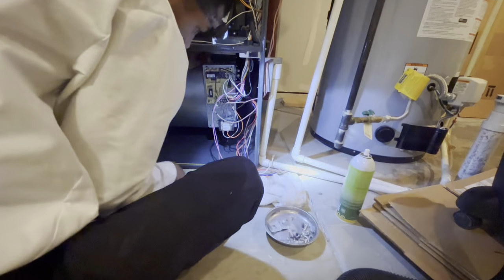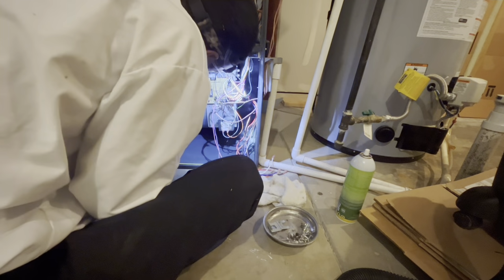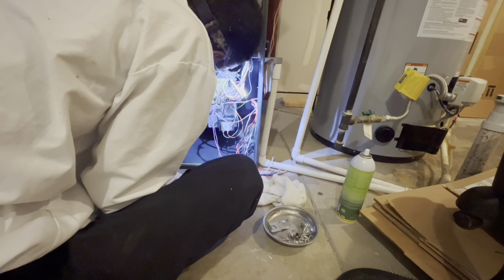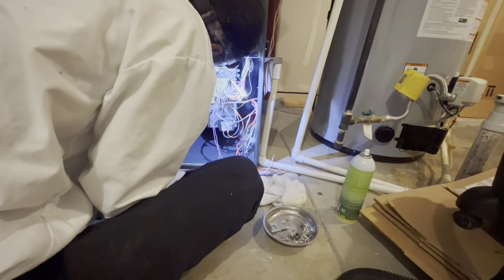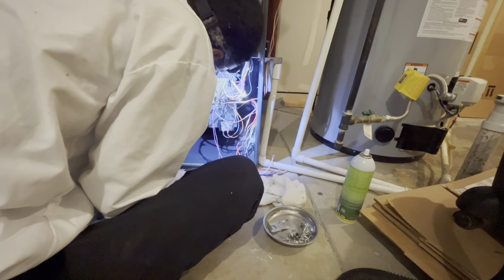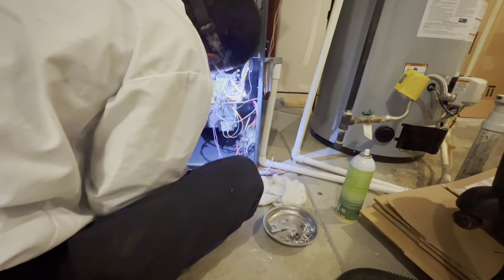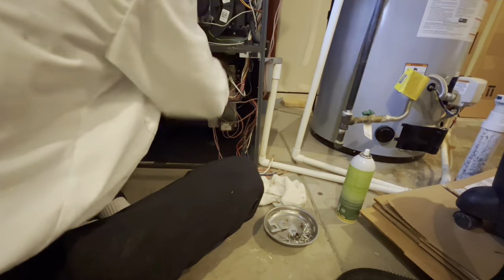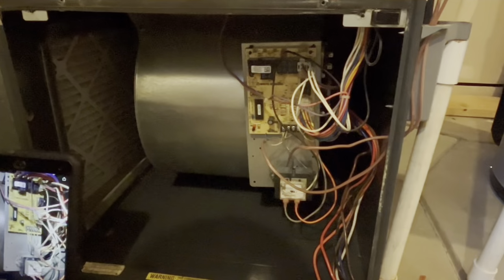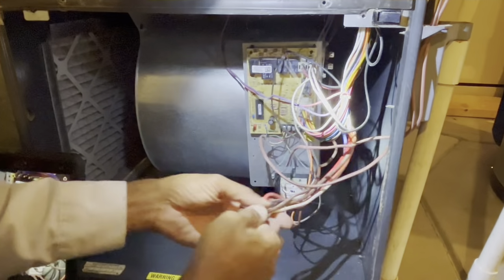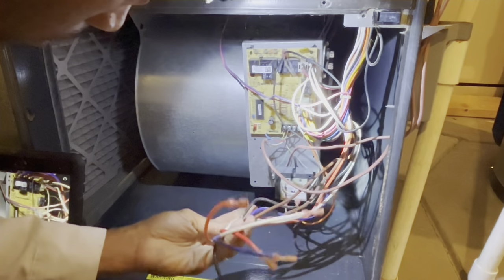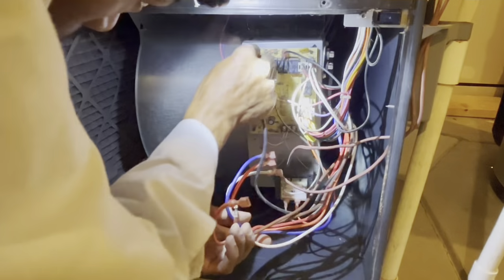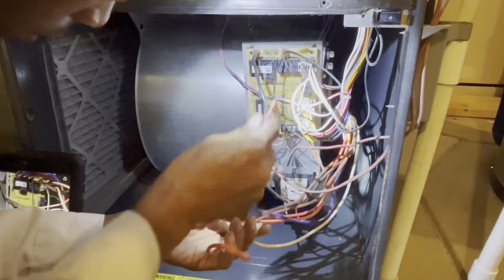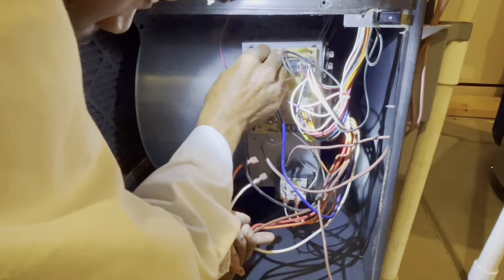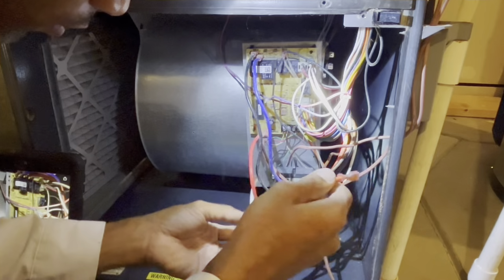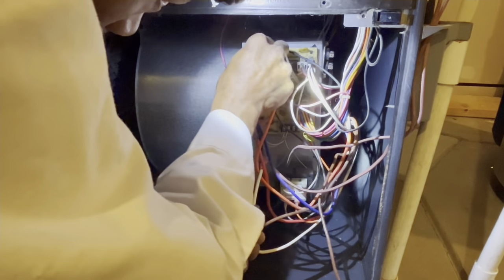This is where having a good headlamp will actually help, you can look at it when you slide in, and just make sure you take your bolts and tighten them up by hand good. And make sure that wiring is coming towards the front of the furnace. Once you get everything nice and tight, then you can start mounting the circuit board back on that housing. Some circuit boards will actually mount to the furnace, so it all depends. And you should always have a picture or diagram where all the wires were connected.